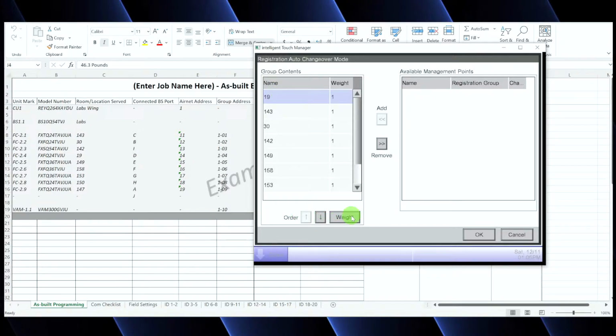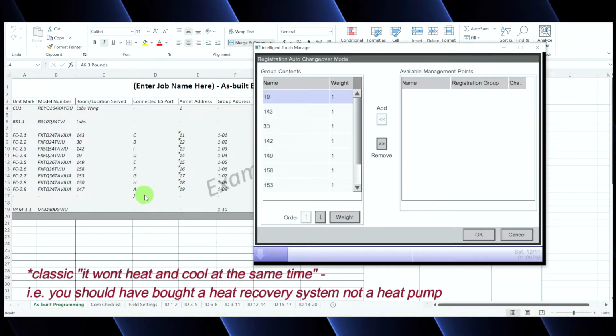The weight button really comes into play when I need to give each unit a particular weighted value, because maybe I have a heat pump system. I don't have a heat recovery. If you guys recall from previous videos, heat recovery systems can heat and cool simultaneously. Basically, every port on the branch box is its own individual mini heat pump. Port C can heat, port B can cool, port I can heat, do whatever it wants all simultaneously. Well, if you don't have that and you just have a heat pump because whoever designed it, whoever paid for it, was cheaping out and did the heat pump solution instead, well, guess what? All these units are going to be in heat, or all these units are going to be in cooling.